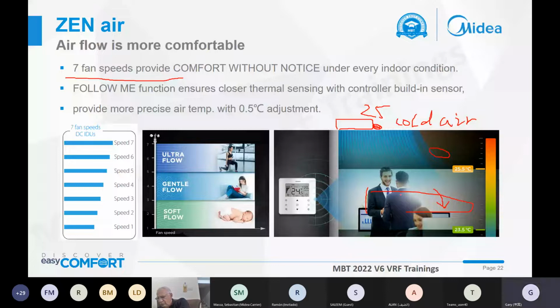So to avoid these situations, we have the follow me function in our controller. When you use this function, the unit doesn't read the sensor of the unit. It will read the sensor in the wired controller. As the wired controller is normally installed near the height of people, the temperature in this area will be closer to the feeling of the people.